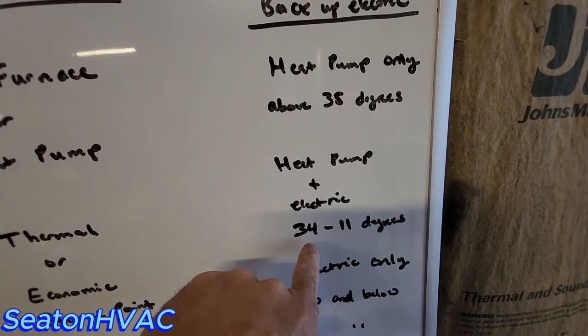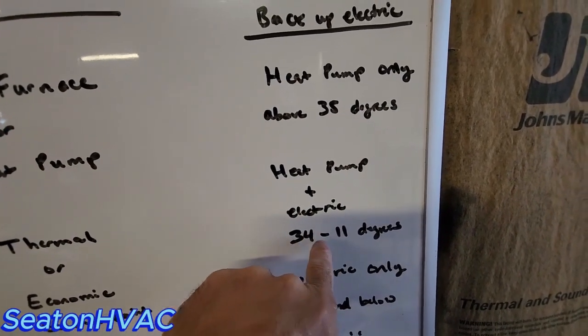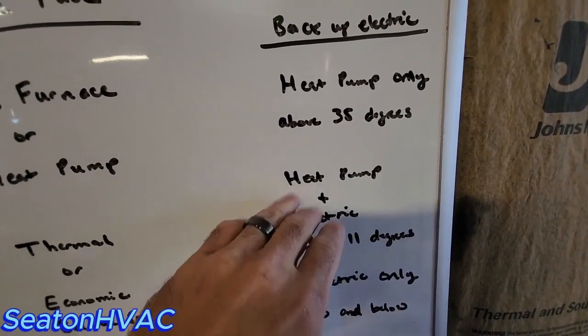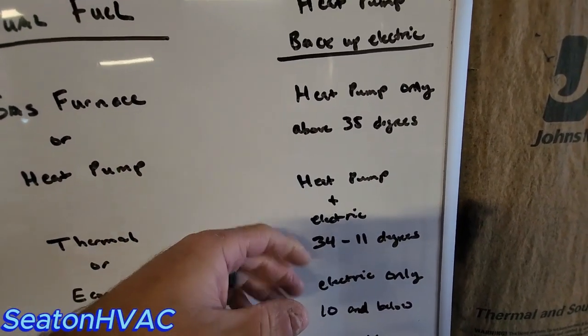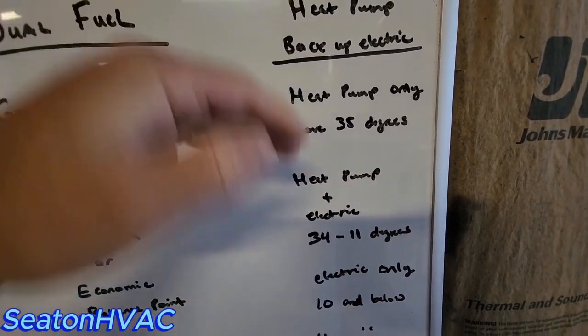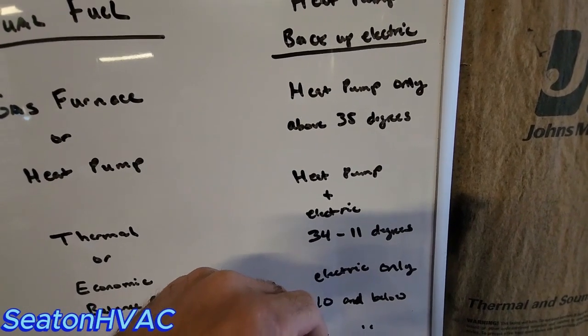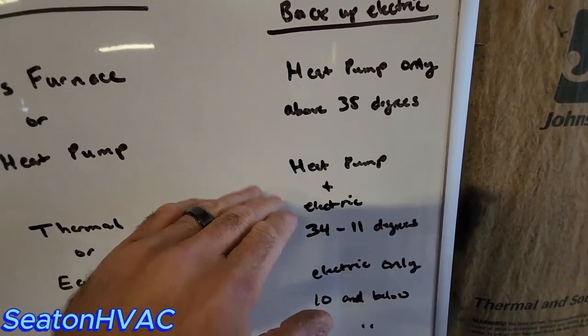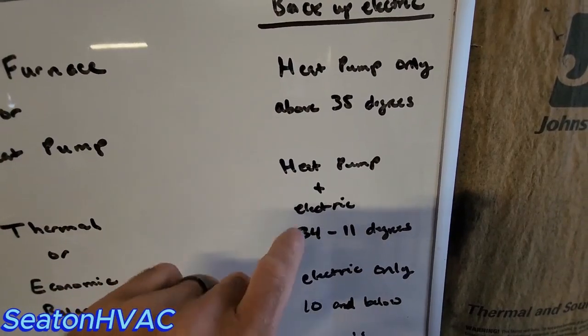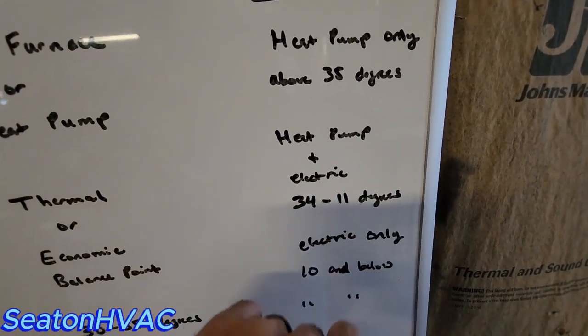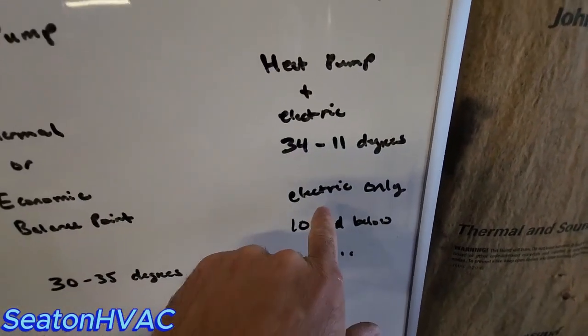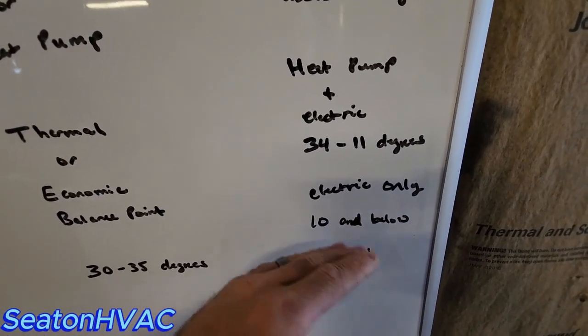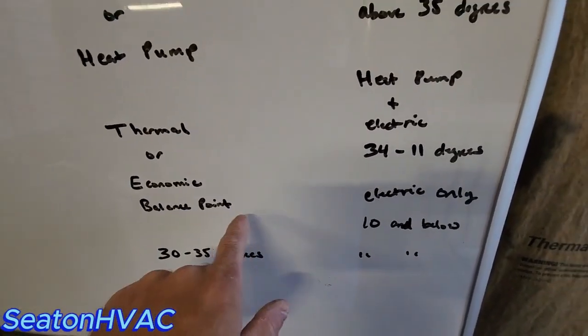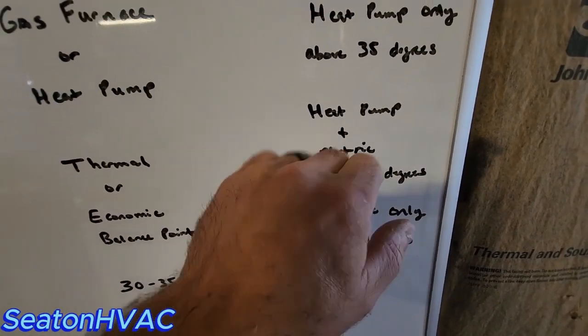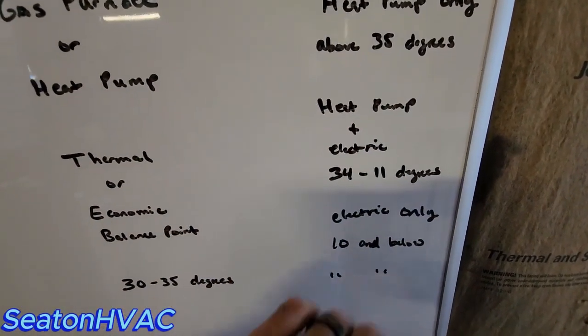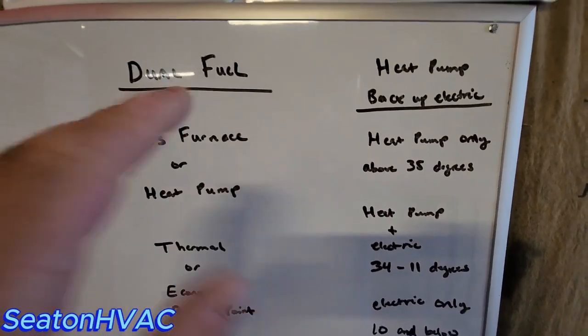Then most systems between 34 and 11 degrees are heat pump and the electric backup running at the same time. They can run at the same time because your electric heat strips are on the discharge side of your evaporator coil, so it's not going to affect the pressures as far as your refrigeration side of the system, okay? So heat pump electric, 34 to 11 degrees, both at the same time. And then I like to set them up so it's electric only 10 degrees and below. Again, you can see what the thermal and economic balance points are on that too, but most heat pumps are not going to run very well below 10 degrees from what I've seen. So let me know if that makes sense to you guys.